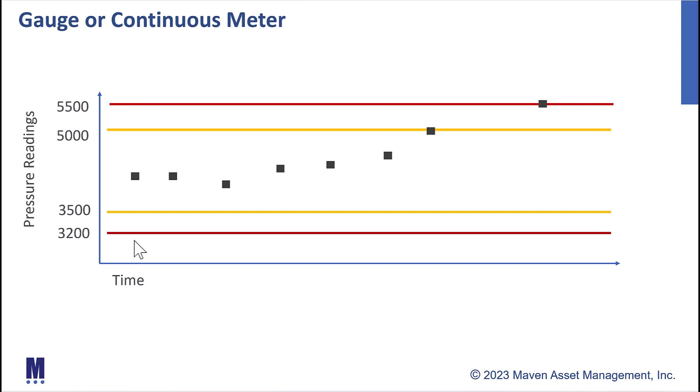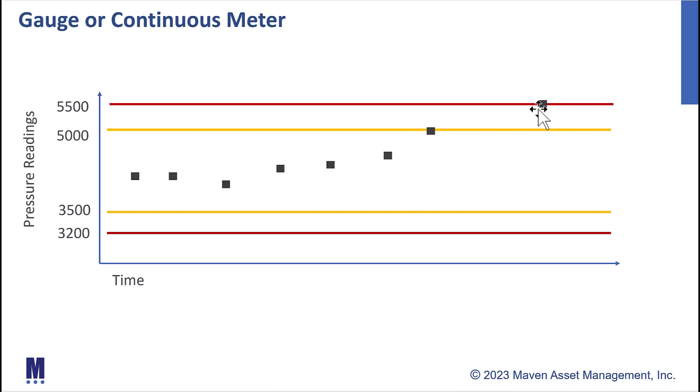Now when we look at these particular readings, we can see we're in a pretty good steady state here in the middle, but then something happened over time and we're starting to creep up into the top. And then our last meter reading here hit 5,500, which is our upper action limit, so we want to take action.